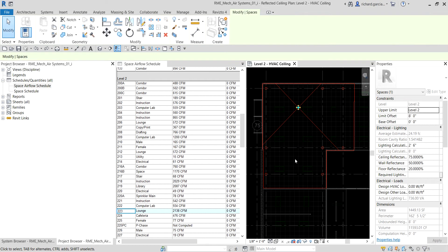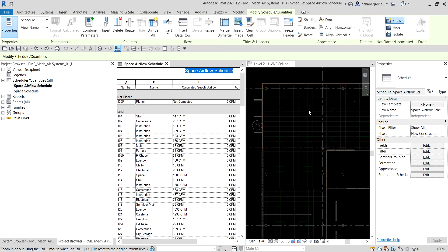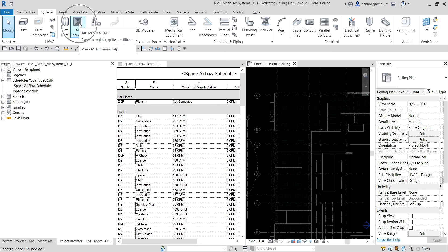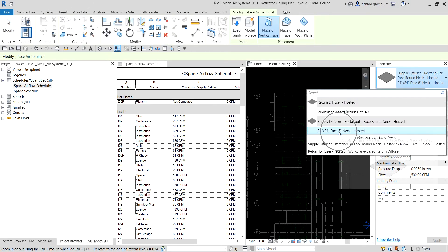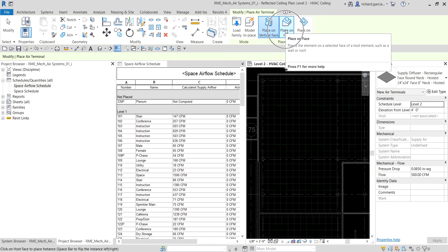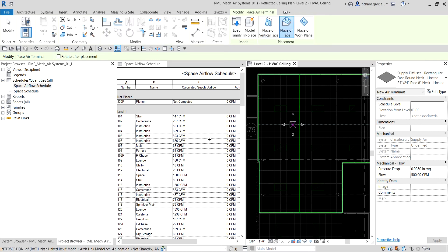I'm going to place a supply air terminal. As you can see it's still zero because we haven't placed the air terminal yet. I'll go to the Systems tab, select Air Terminal, and from the type selector choose the supply diffuser — a hosted family. If your pointer says 'cannot,' make sure the placement option is set to 'Place on Face' so the air terminal will be placed properly on the ceiling.